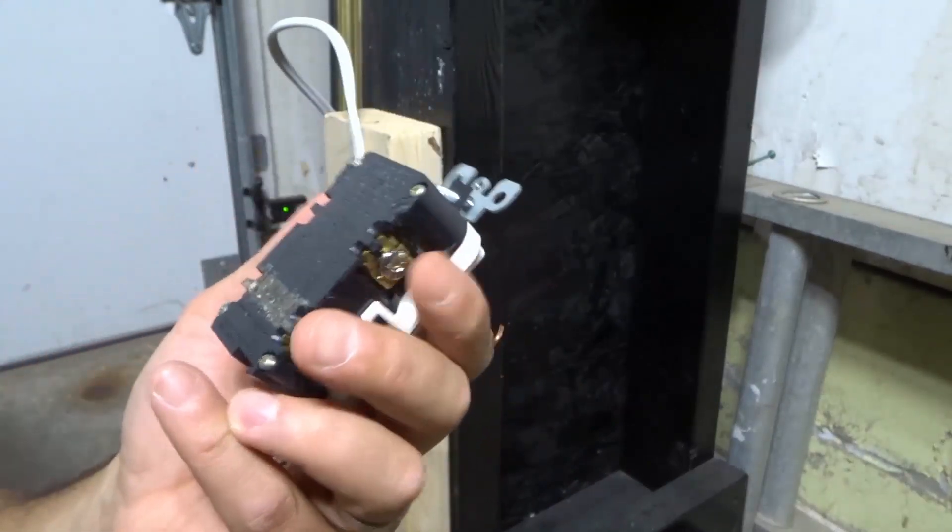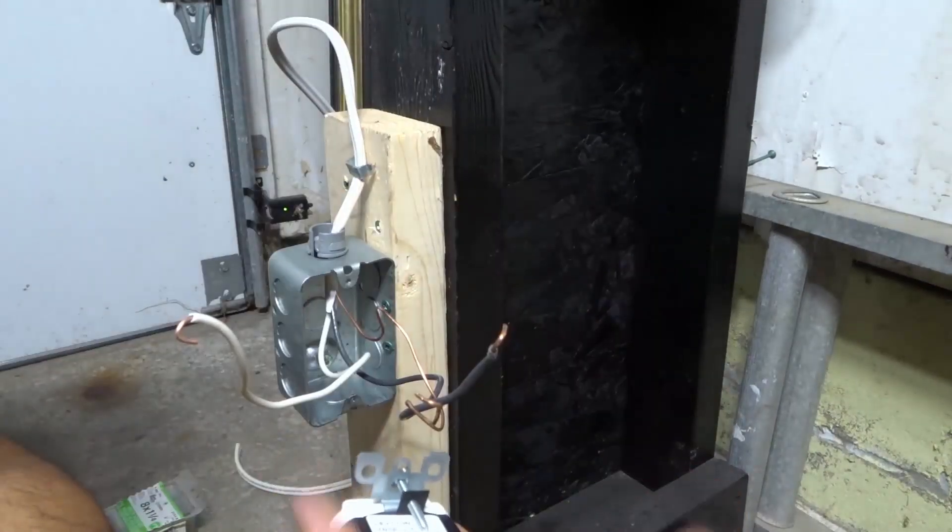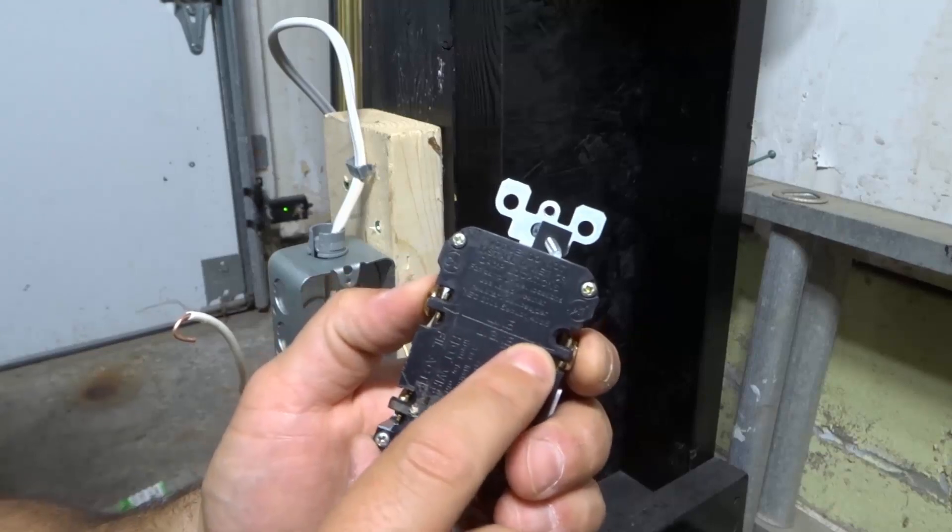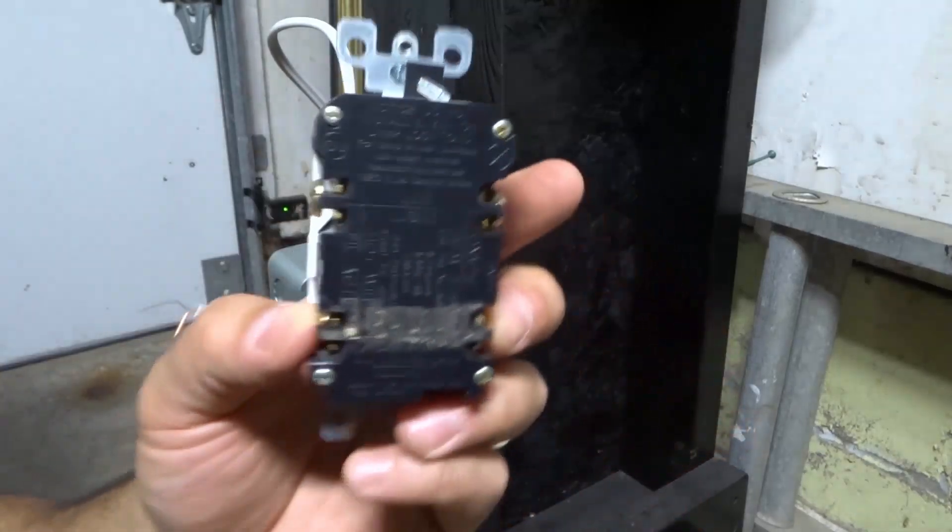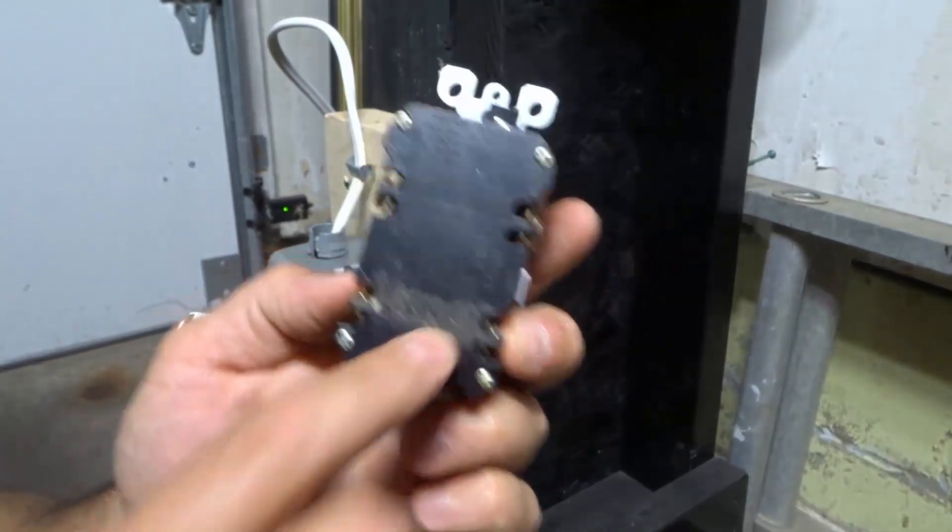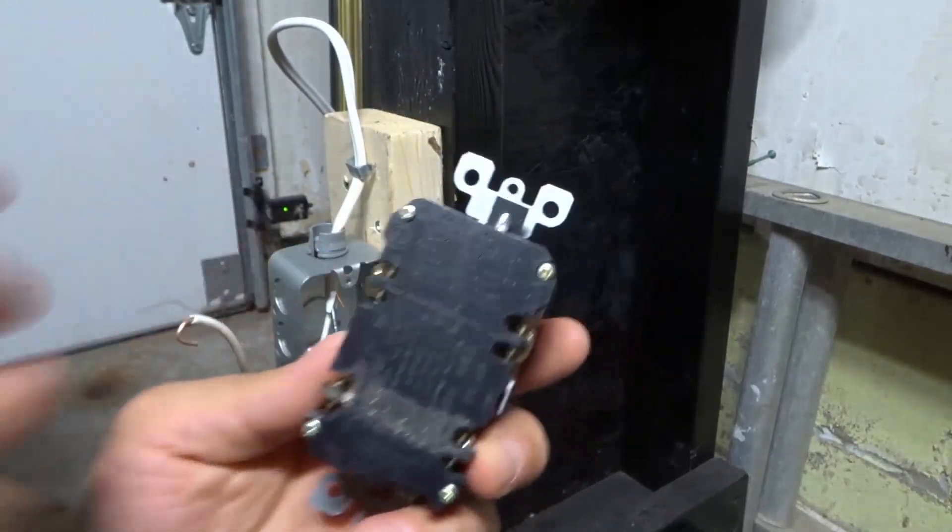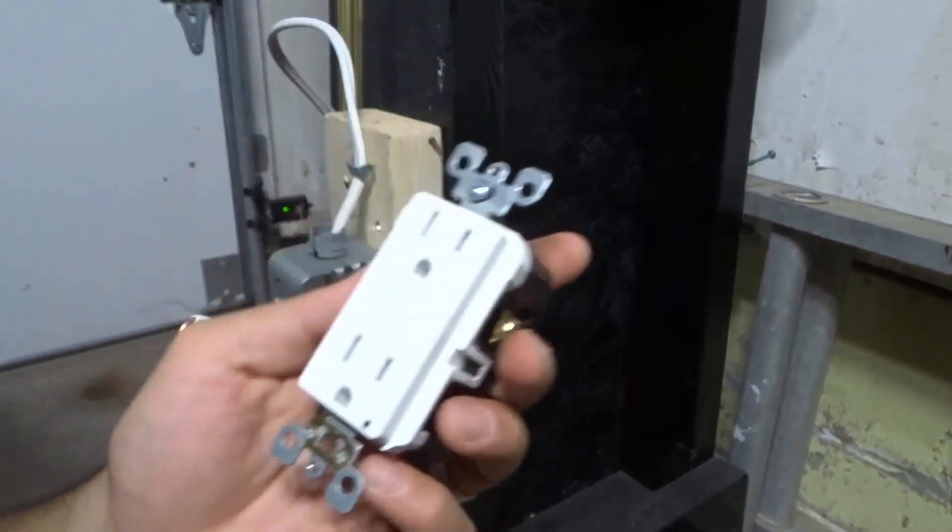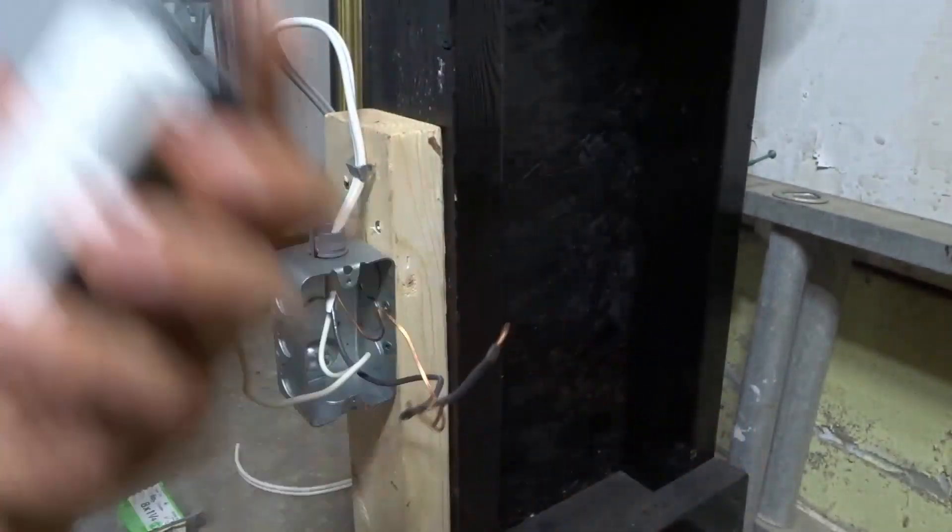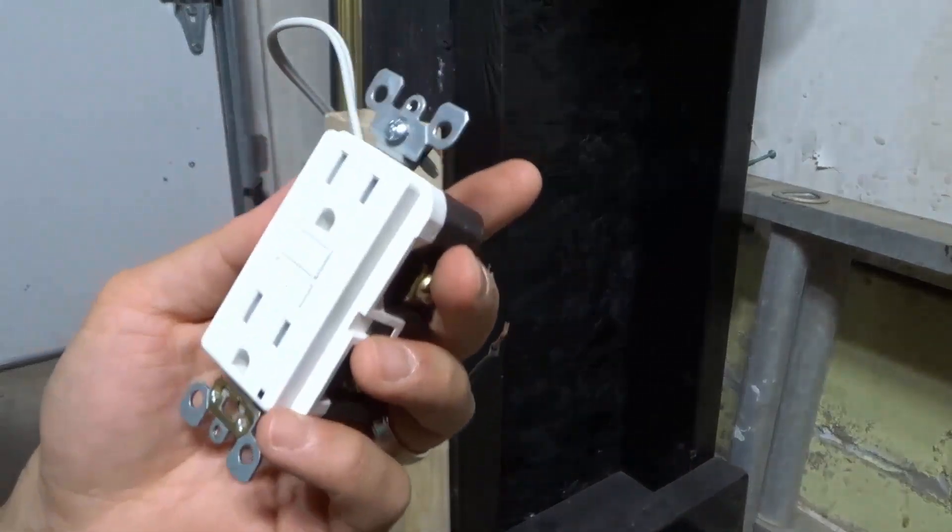The line is the power that is coming from your electrical panel. So your electrical panel feeds the power to the line section of your GFCI. If you want to connect other outlets after your GFCI, you're going to put those on the load section. If installed properly, those outlets on the load section should be protected with the same GFCI moisture and dampness protection.